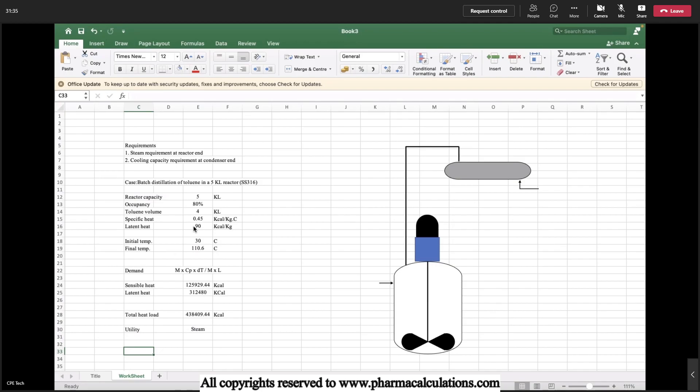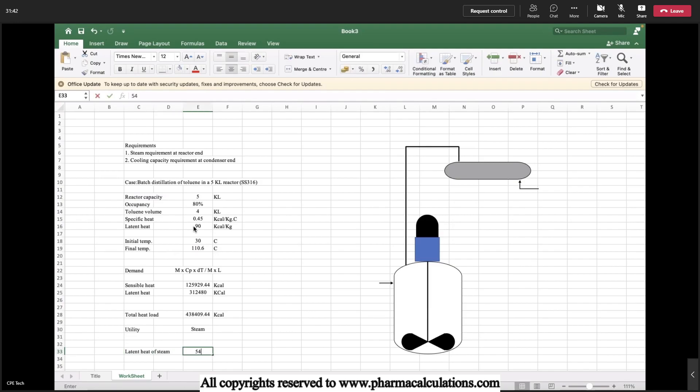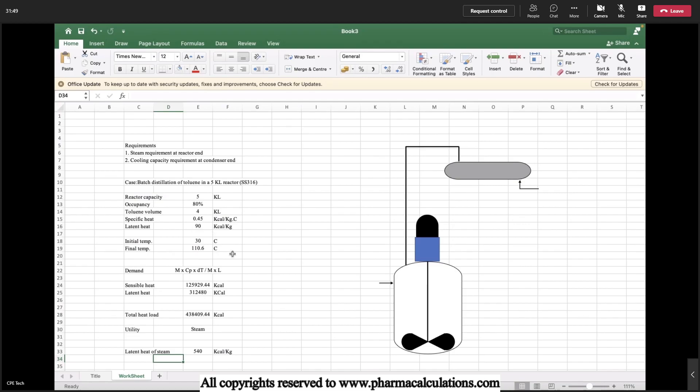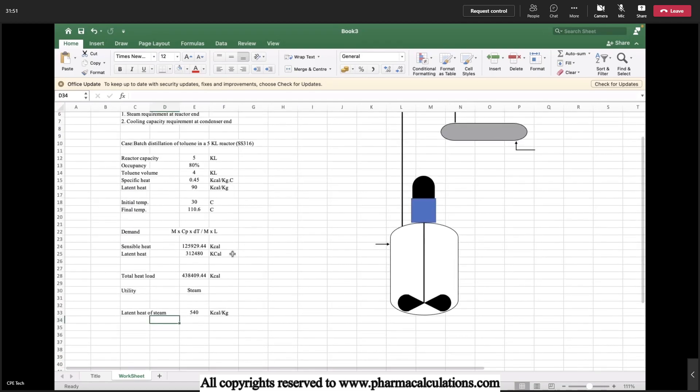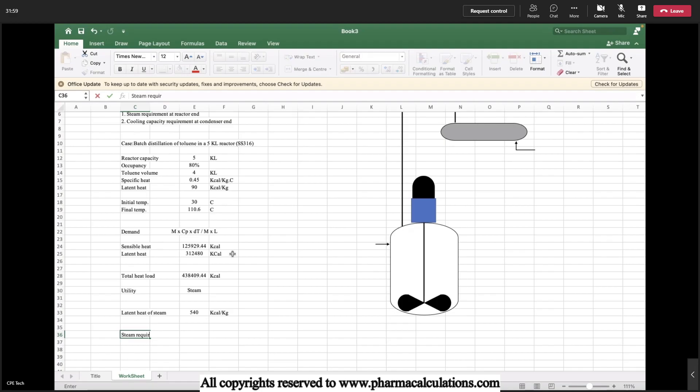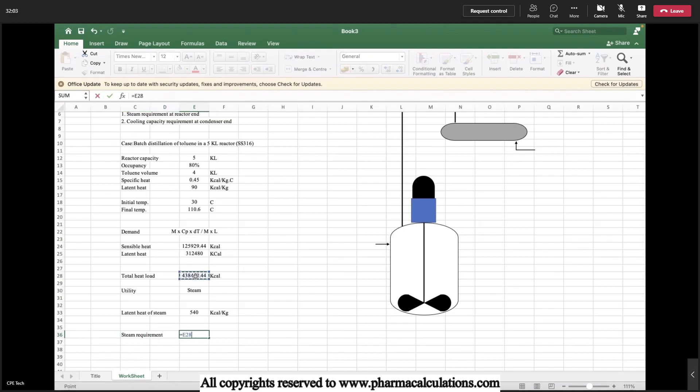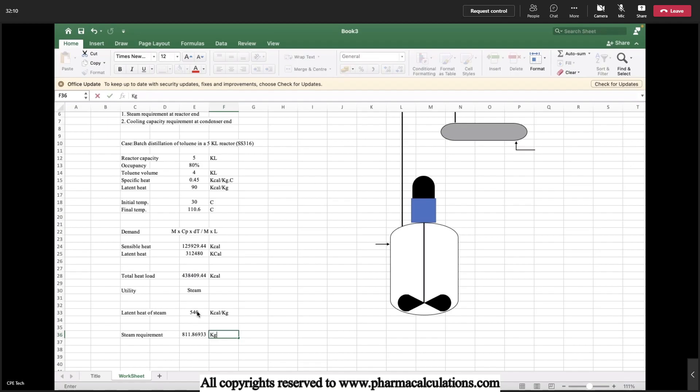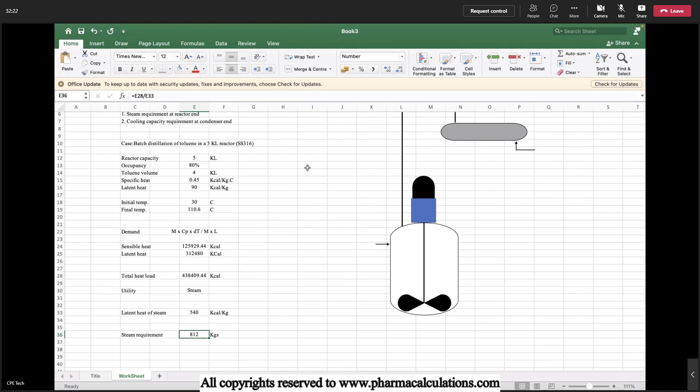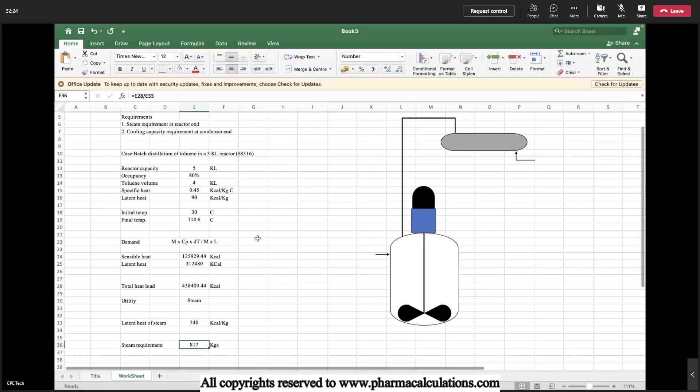Steam will have a latent heat of 540 kilocalories per kg. So the total amount of steam required is the total heat load divided by latent heat of steam, that is 540 kilocalories per kg. So here we will be getting the total steam consumption. It's nothing but around 812 kg of steam. This is the steam requirement for total completion of a distillation.